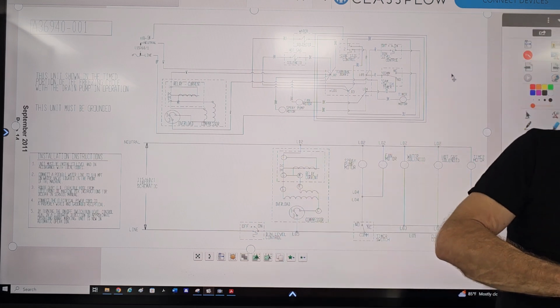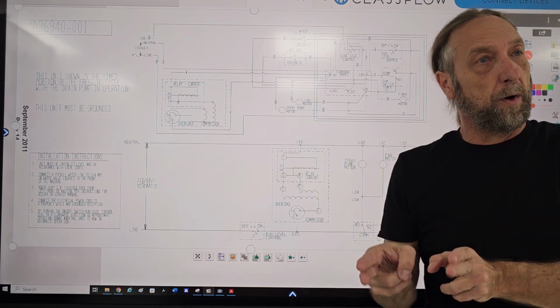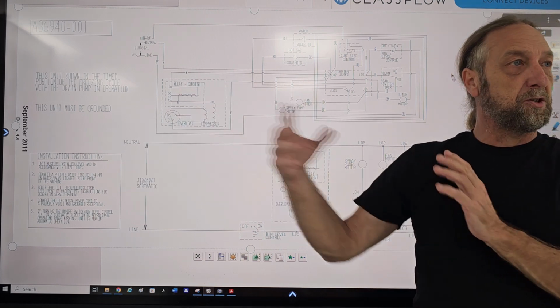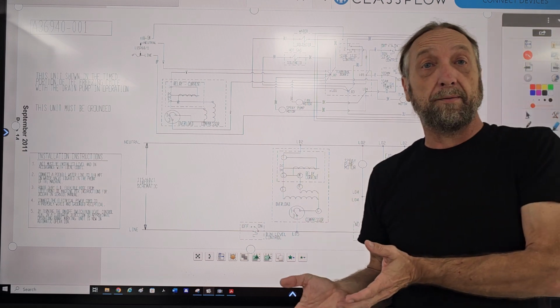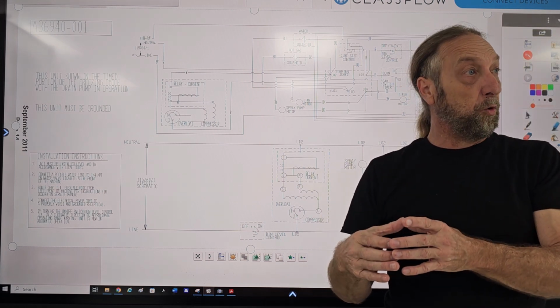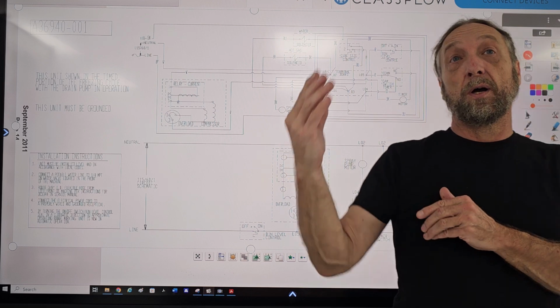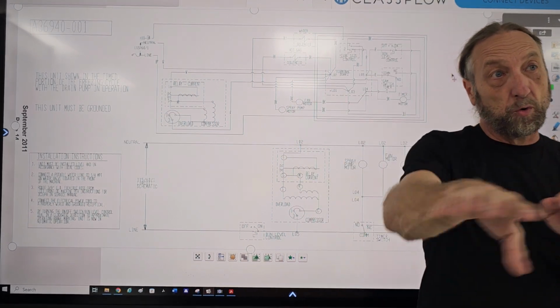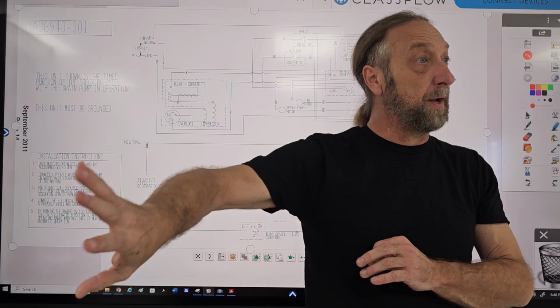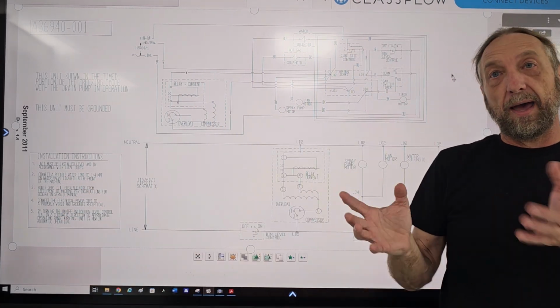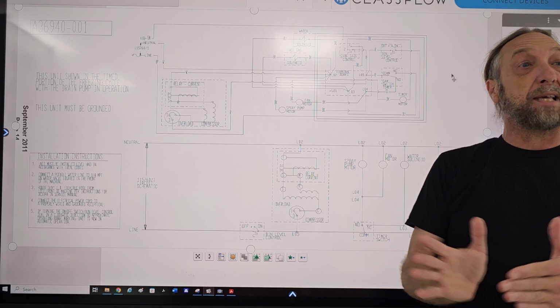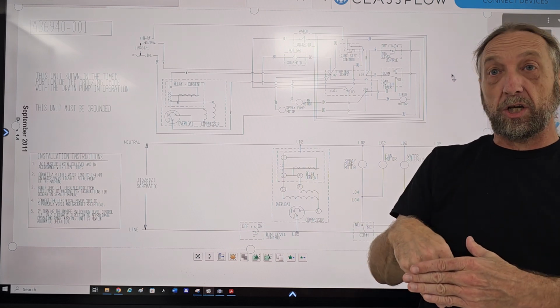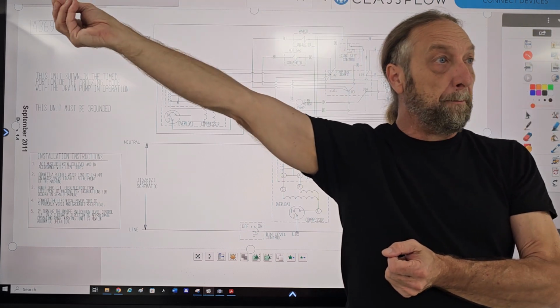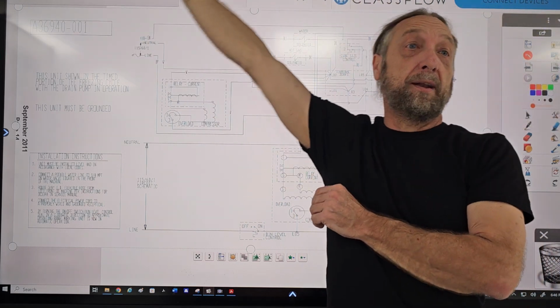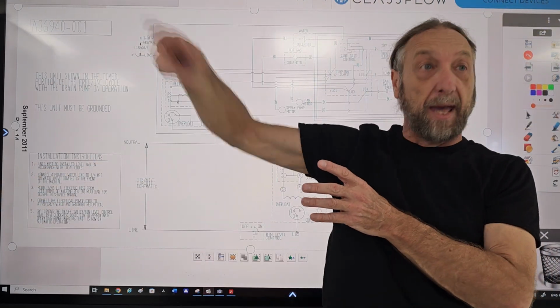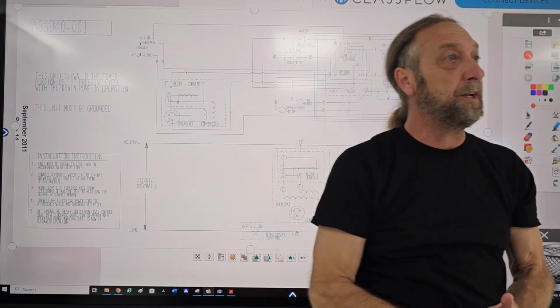These machines are normally designed to be gravity drain — you have a drain in the floor, or the unit is attached to an exterior wall, so you just drill a hole and run the hose outside to let the water drain. But if you don't have that ability, a condensate pump built into the machine can pump the water out instead. You could run the line up into the attic and across the house, and the pump would mechanically push that water out — you don't have to rely on gravity to drain it.